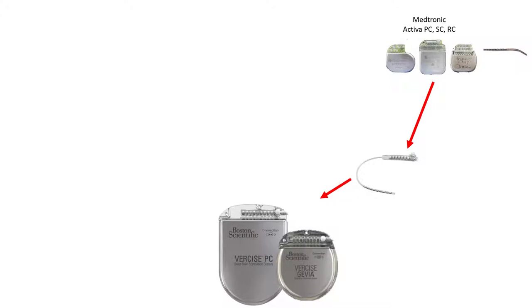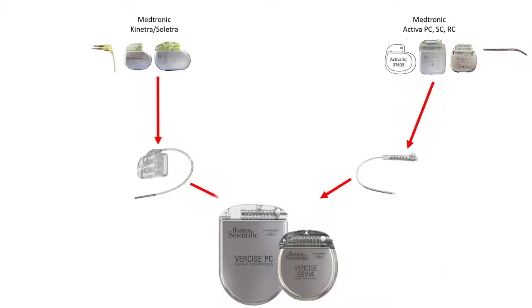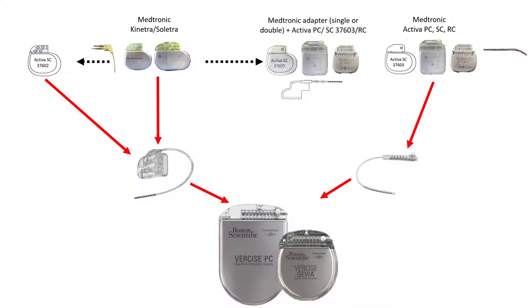So, if the patient started with Activa RC, PC or SC 37603, then you just use the Boston adapter for modern connections. If the patient started and still has Medtronic Kinetra or Soletra, then you use the Boston adapter for all contacts. The same is true if the patient has changed to an Activa SC model 37602 with the old connection. If the patient has changed to a Medtronic single or double adapter connected to Activa RC, PC or SC model 37603, you can retain this adapter and add the Boston adapter for modern connections, or you can replace the Medtronic adapter with the Boston adapter for all connections, which is probably a better option.